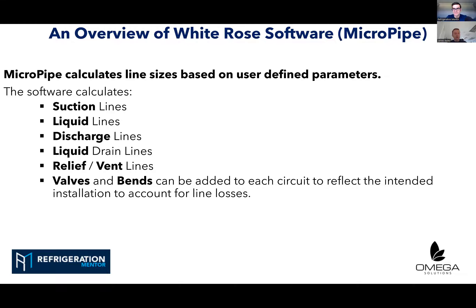The software works on a basis of user-defined parameters — if you put garbage in, you get garbage out; good things in, you get good results out. The software calculates suction, liquid, discharge, liquid drain, relief, and vent lines. For every single circuit, we can add vents, valves, and bends. Effectively, we can mimic a real-life installation and account for those small line losses that can accumulate to quite a big loss overall in a large distributed system.